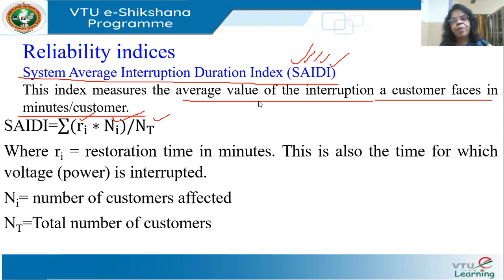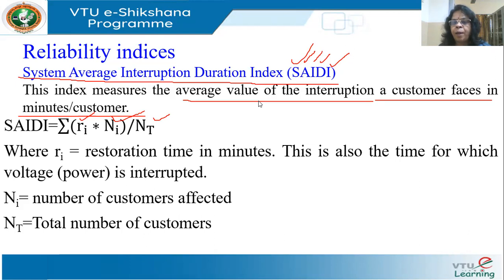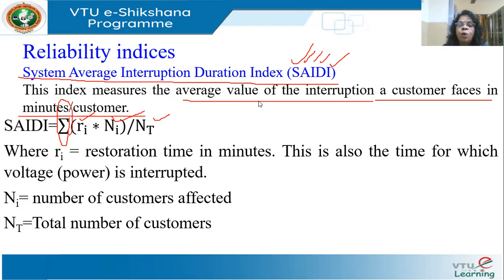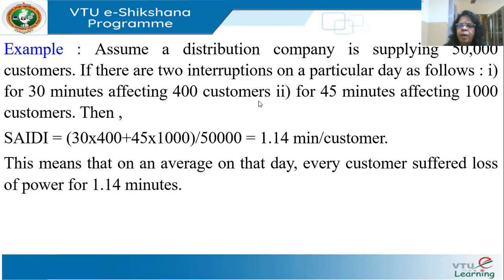Because today some customers may be affected, tomorrow others may be affected — today the feeder supplying area X got affected, tomorrow the feeder supplying area Y may get affected. So RI is the restoration time for every interruption. For each interruption, what is the restoration time and how many customers have been interrupted? The sum of all that as a ratio of the total number of customers is called SAIDI — System Average Interruption Duration Index.